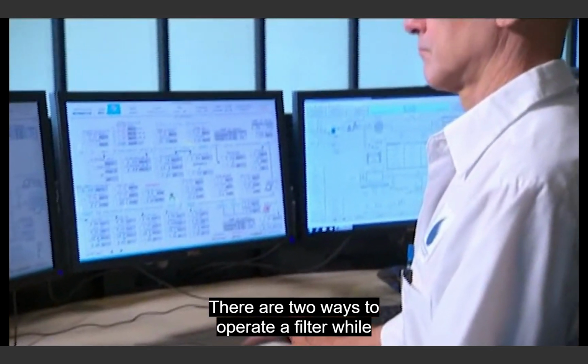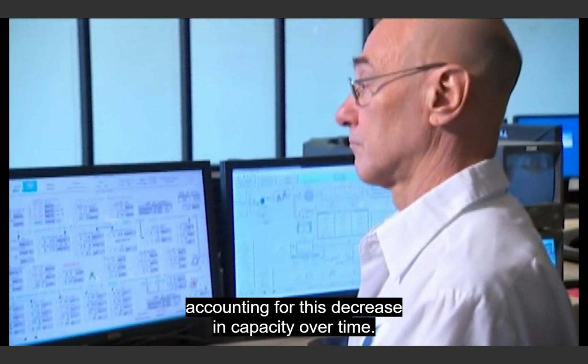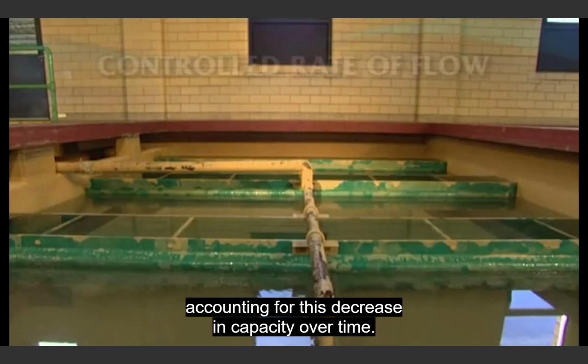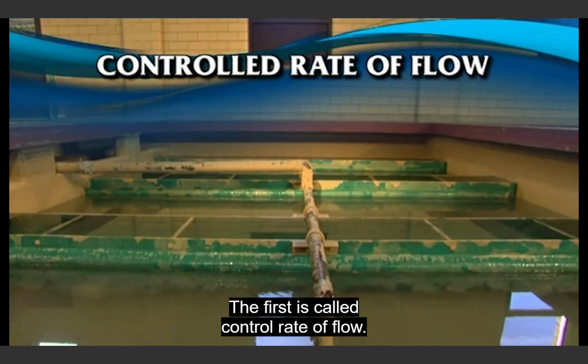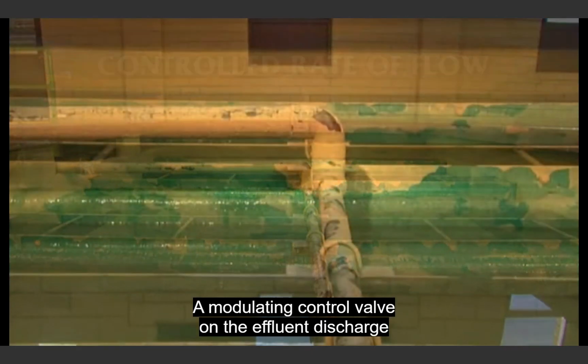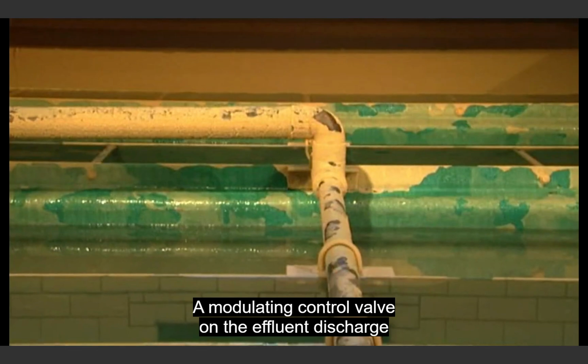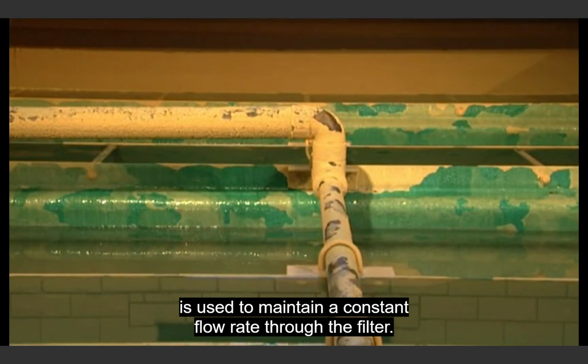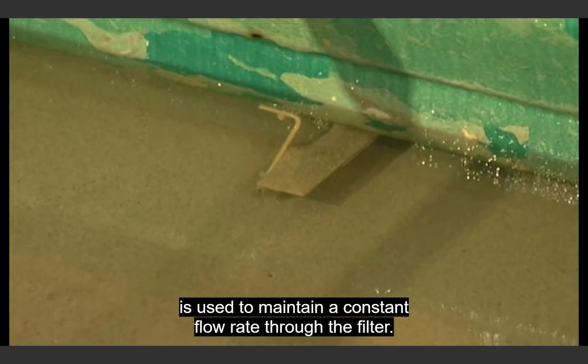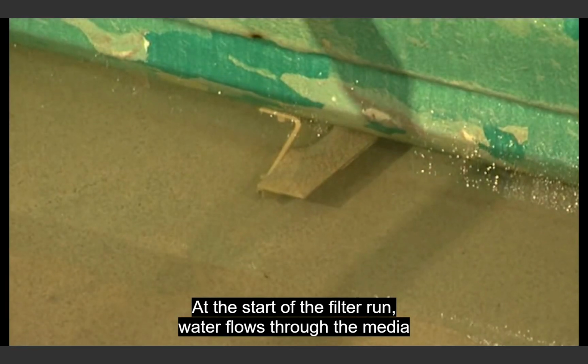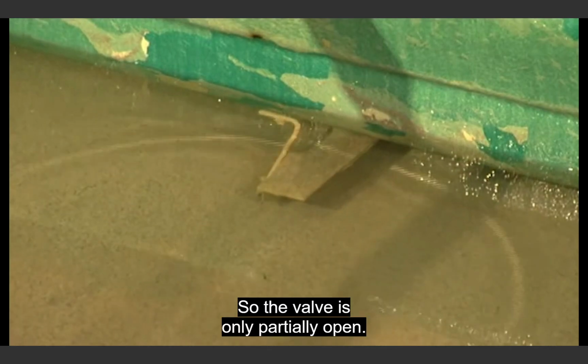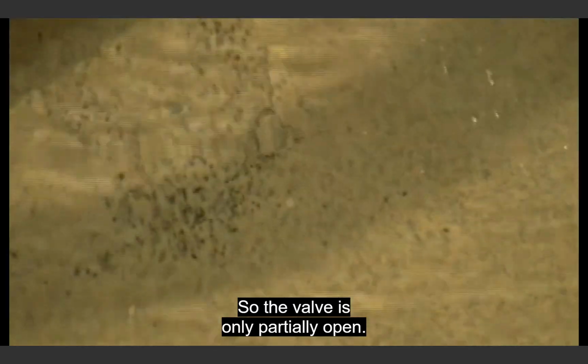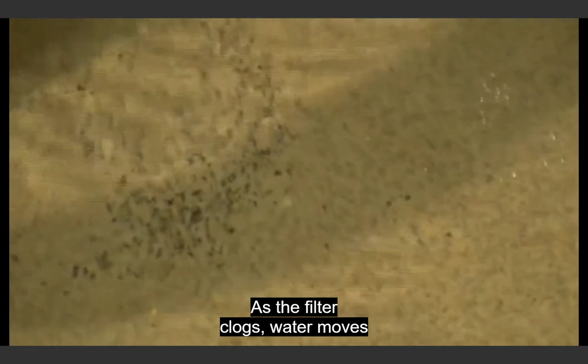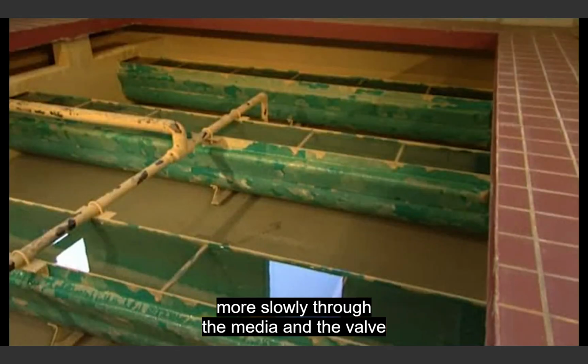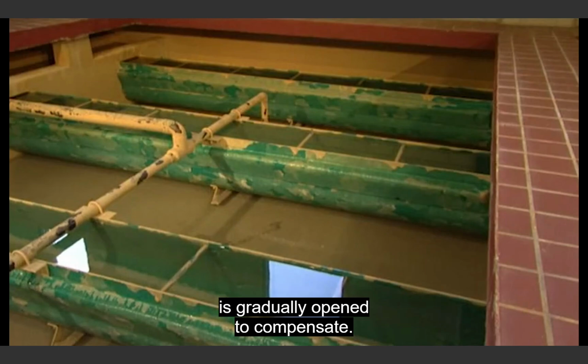The more material a filter accumulates, the less efficiently it is able to filter. There are two ways to operate a filter while accounting for this decrease in capacity over time. The first is called controlled rate of flow. A modulating control valve on the effluent discharge is used to maintain a constant flow rate through the filter. At the start of the filter run, water flows through the media easier, so the valve is only partially open. As the filter clogs, water moves more slowly through the media and the valve is gradually opened to compensate.